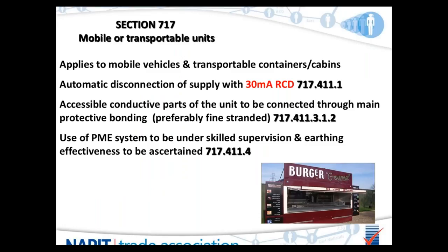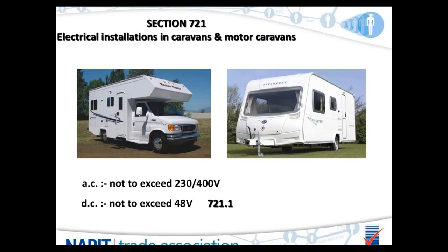Section 717 covers mobile or transportable units — mobile vehicles, transportable containers and cabins such as catering units. Additional guidance is available in BS 7909 for temporary electrical systems. All such installations require automatic disconnection of supply via a 30mA RCD. In accordance with Regulation 717.411.3.1.2, all extraneous conductive parts such as the structure shall be connected by the main bonding conductor direct to the main earthing terminal within the unit. PME is only permitted if the installation is continuously under the supervision of a skilled person and the effectiveness of the earth is confirmed before connection.